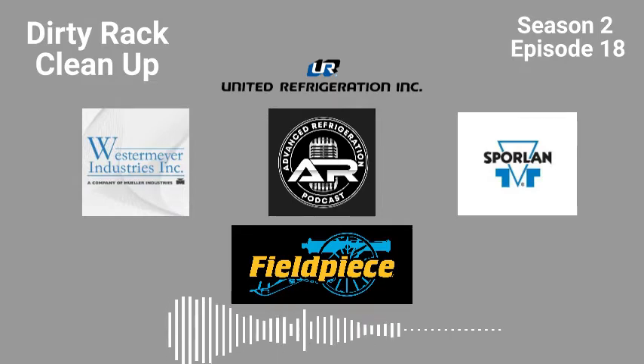So I will go through, and depending on how dirty the rack is, say if it's filthy and I'm getting oil issues and plugged screens, I start from the beginning. I get my liquid filters changed. I get that new assembly in there. Then depending on how bad it is, I will drain down the compressors by pumping the oil back into the reservoir or wherever. I will pull the sump screens and clean all of them, get everything vacuumed down, get all the garbage out of the bottom of the compressors, and get the oil cleaned up.